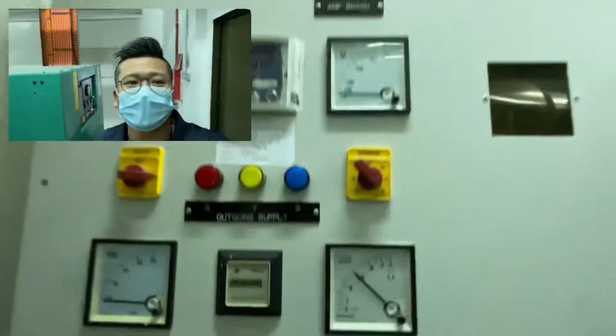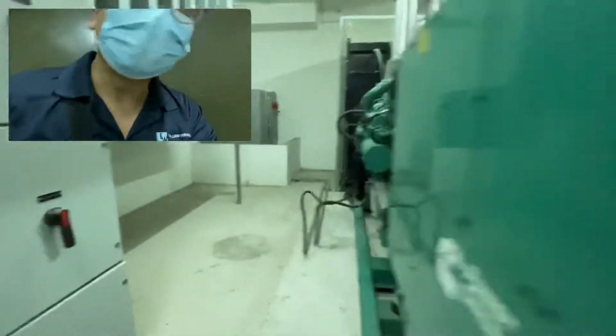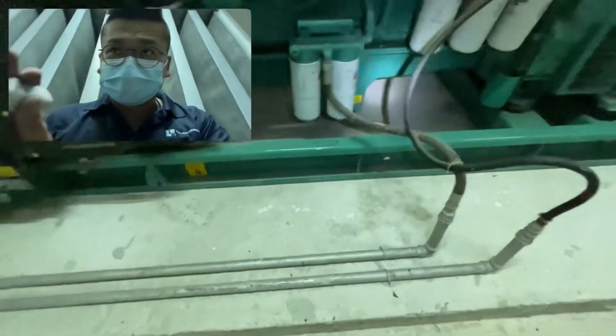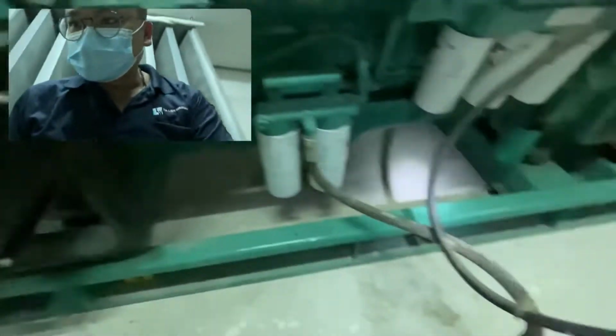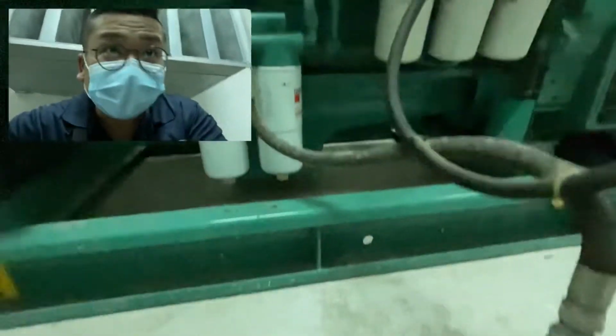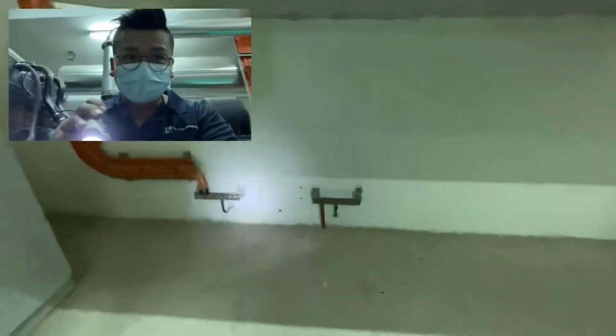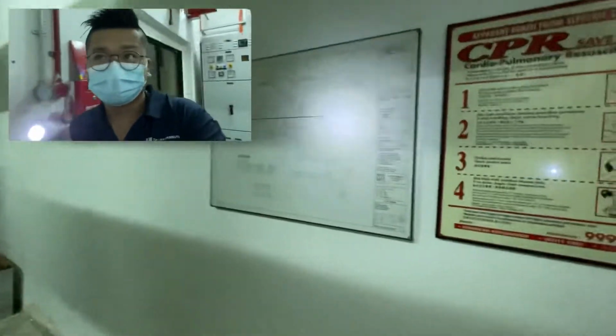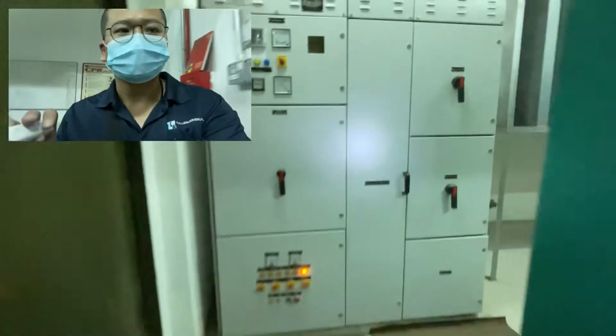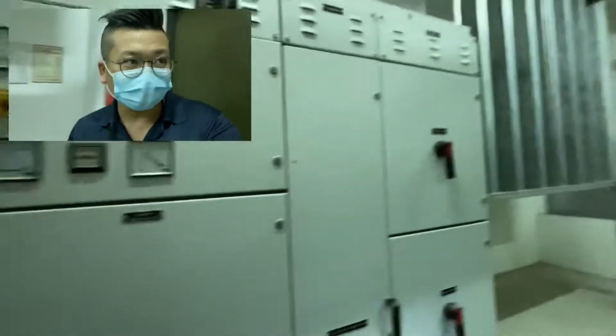Okay, automatically stop. Let's check back the genset charger voltage. Okay, this one is off. Any leakages? No leakages. Condition of the hose, no brittle, no crack. Diesel fuel level about 45%. Okay, nothing unusual, nothing abnormal. There's drawing, first aid chart. Okay, later we'll visit the HV room.